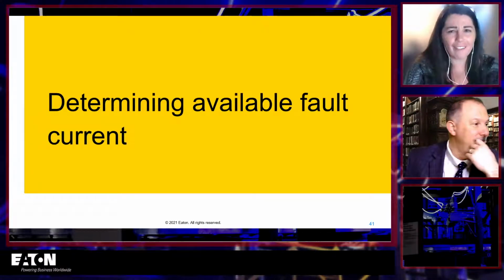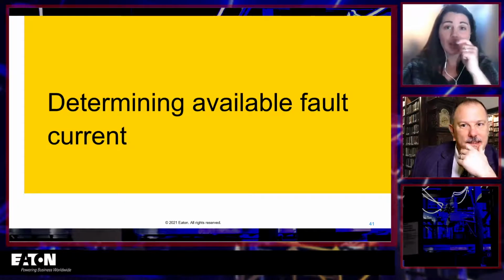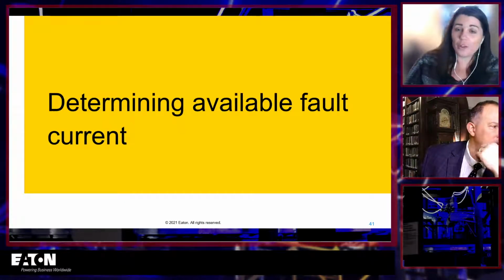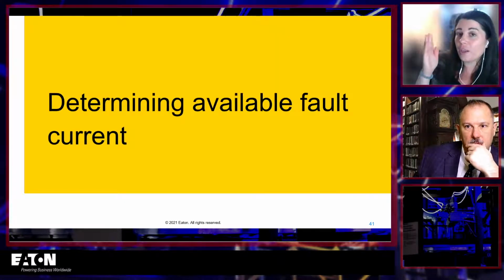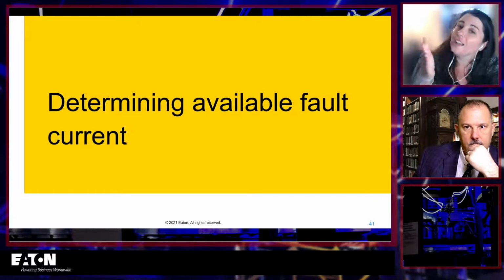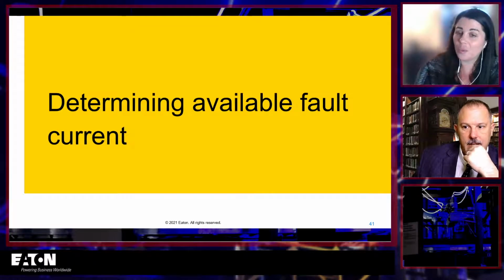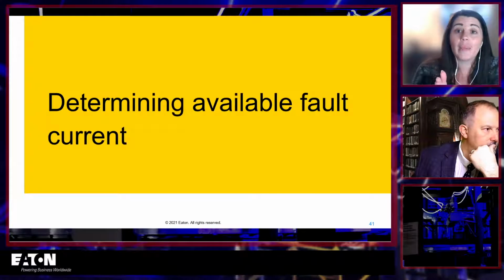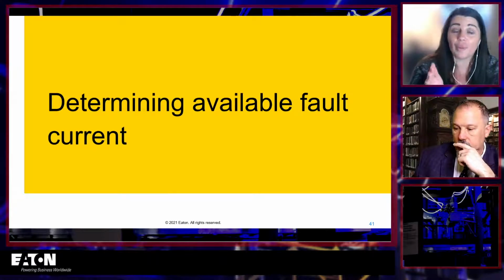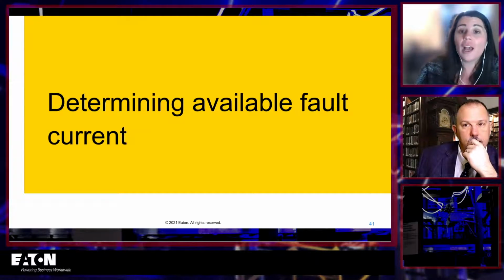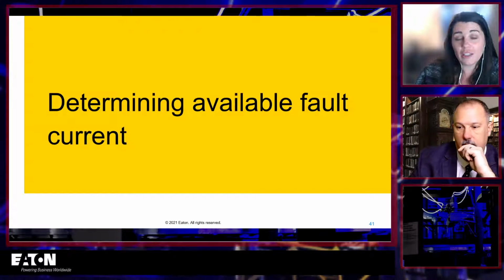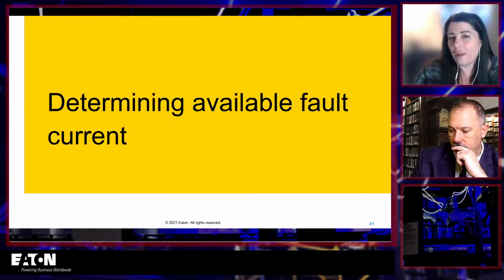Yeah, for sure. All right, so now we'll talk about determining the available fault current, right? SCCR is important, but if we take anything away from the 2017 and 2020 NECs, SCCR doesn't mean anything unless we also know what the available fault current is. So how do we determine the available fault current? There are 3 main ways.